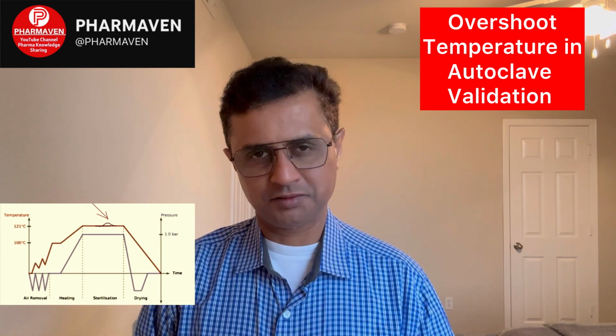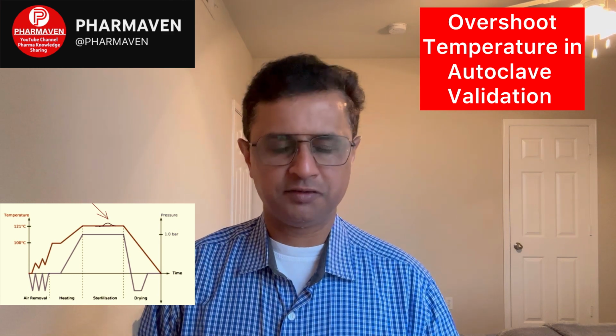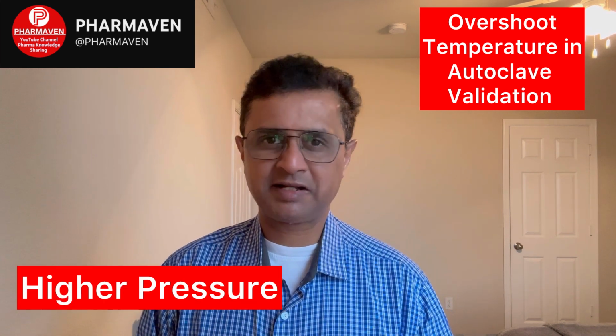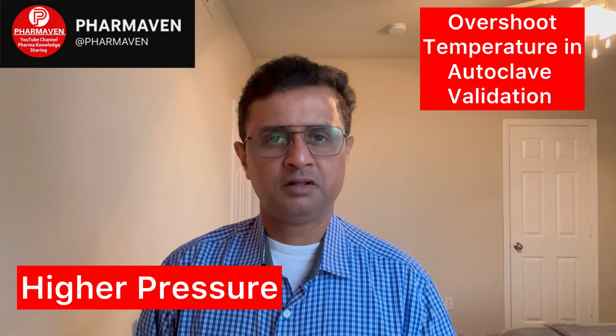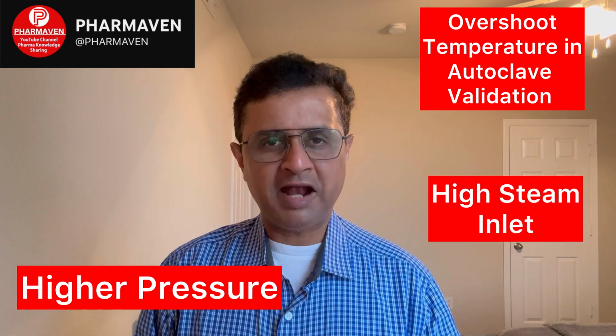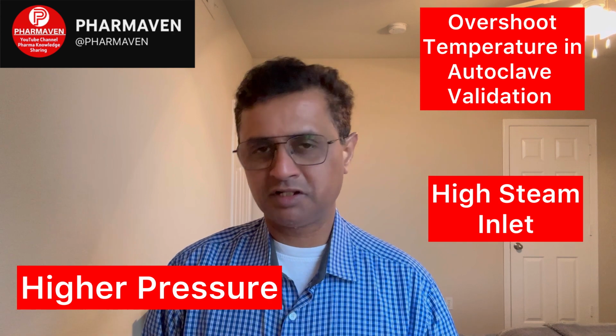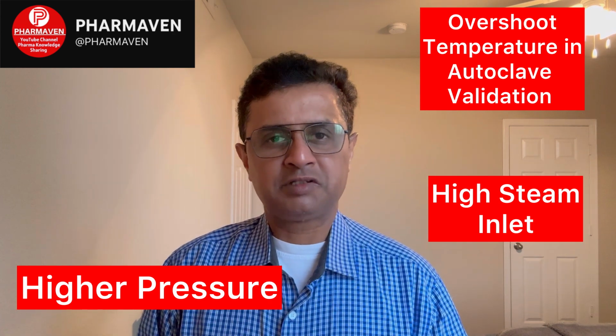Hi, in today's video we will discuss overshoot temperature in autoclave load qualification. So what to do, how to investigate when there is an overshoot temperature in autoclave load qualification. There are mainly two primary reasons which can lead to overshoot. One is higher pressure in the chamber at the specific time when overshoot is observed, or a large quantity of steam might have been injected into the chamber during that specific time. Apart from this, what can be the other reasons and how to investigate, we'll discuss.